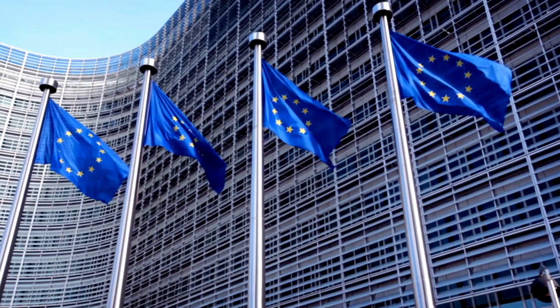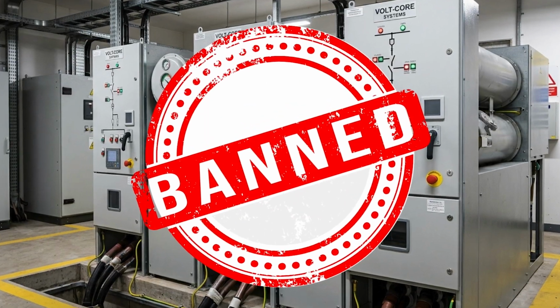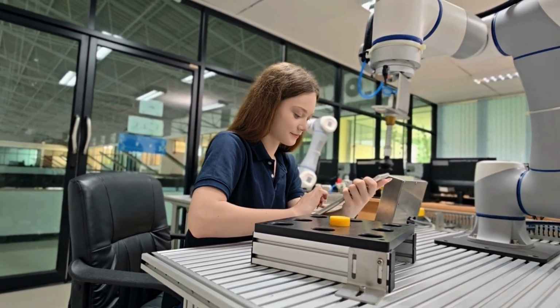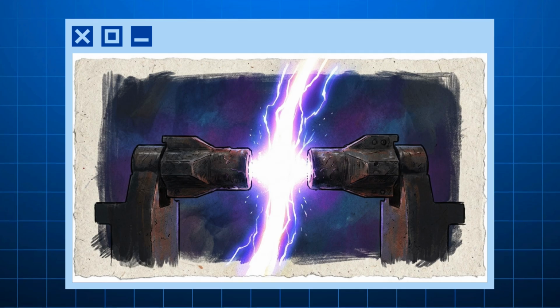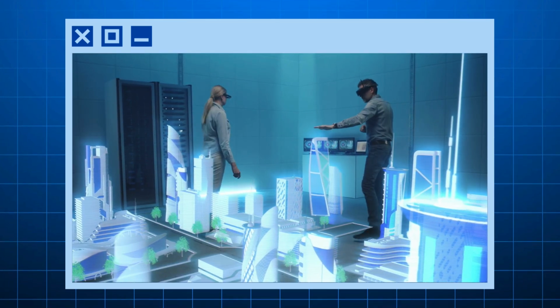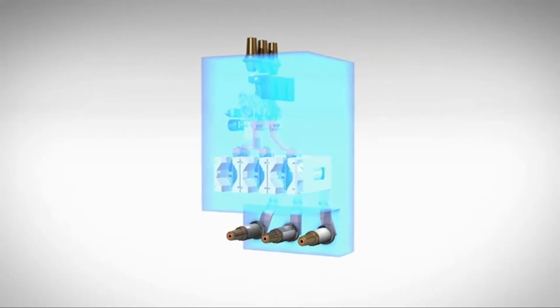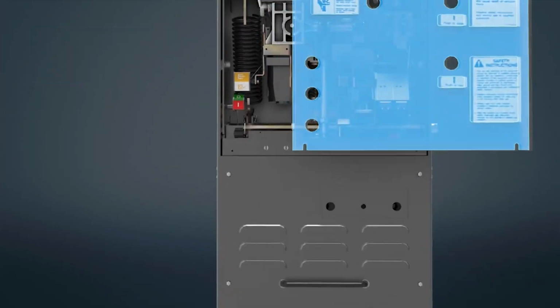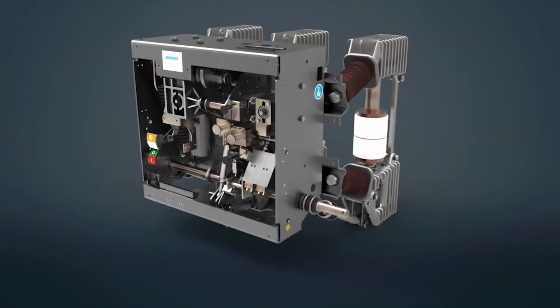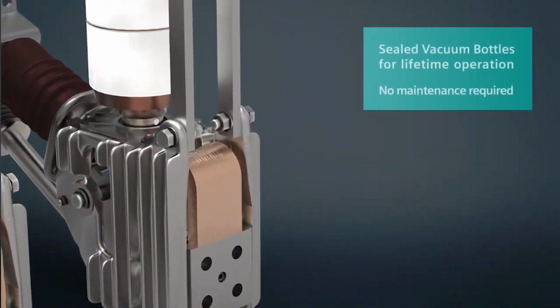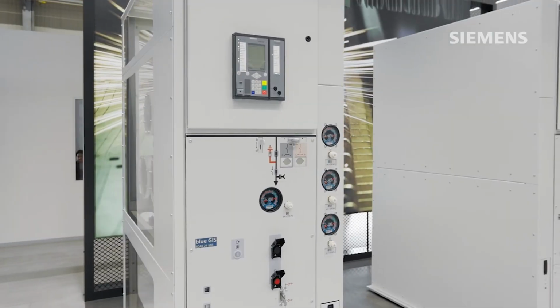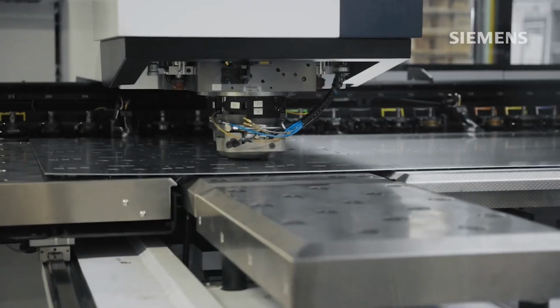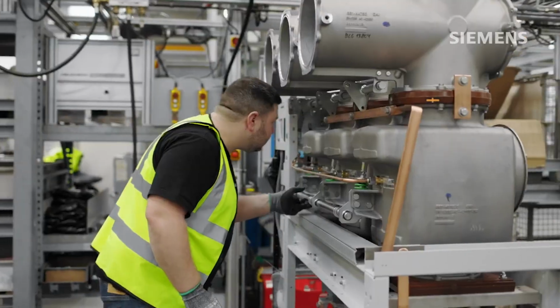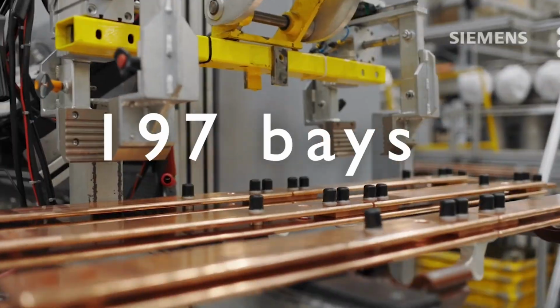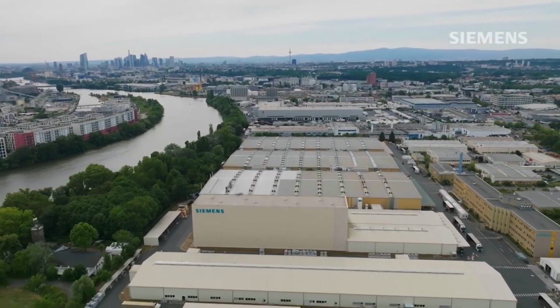This invisible feedback loop is why the European Union's historic ban on new SF6 switchgear officially took effect on January 1, 2026. The industry did not wait for this deadline to scramble for solutions. Because normal air is too light to stop a 66,000-volt arc, engineers had to redesign safety systems from the ground up. Siemens Energy resolved this by combining two technologies: a vacuum interrupter to quench the arc in a sealed chamber with no air to jump through, and highly pressurized clean air, a simple mix of nitrogen and oxygen, to insulate the surrounding conductors. With a global warming potential of exactly 0, this clean air technology has already moved past the laboratory. For the massive 2.9 gigawatt Hornsea 3 wind farm in the United Kingdom, Siemens Energy is supplying 197 bays of this SF6-free switchgear to help power 3 million homes.